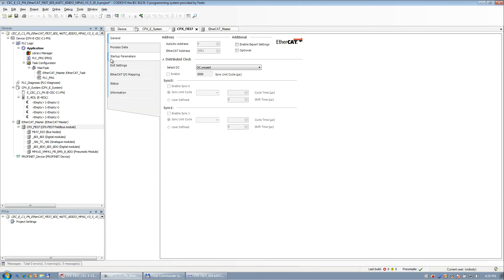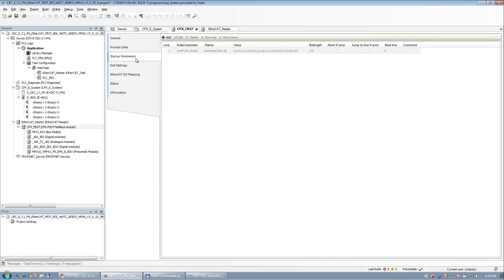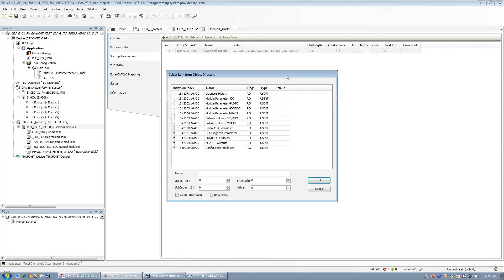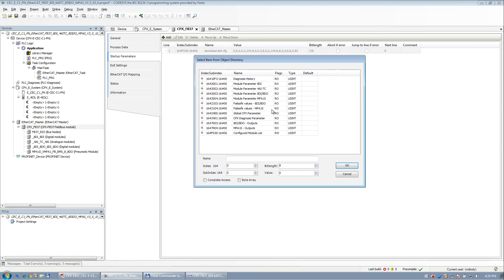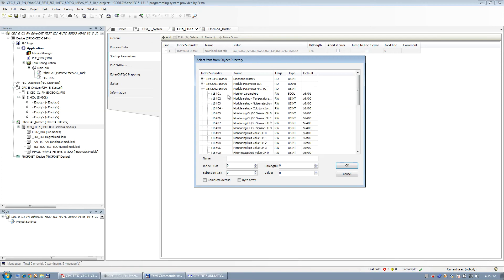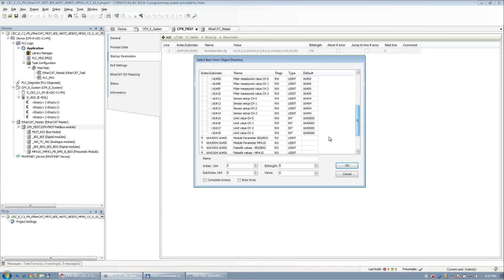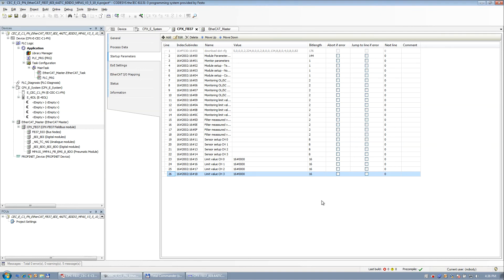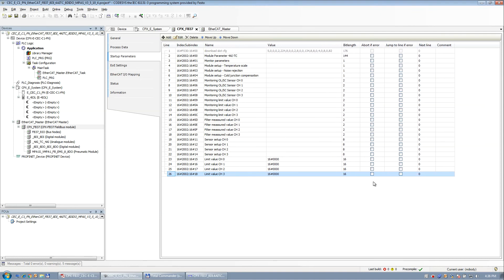So going back to the parameters. So we have startup parameters. And depending what you have module-wise underneath here, it populates this list here. So if you want to have module parameters for this particular analog input card here, you basically select the parameters and you can drag them in. Hit OK. And it populates them for you. Now, at this time, this is service pack 10. And there's a minor bug.